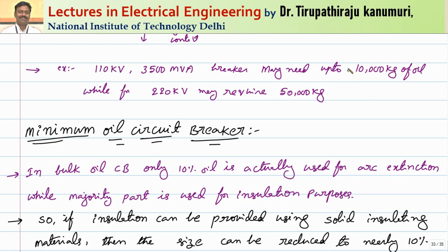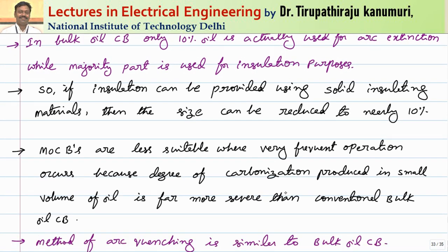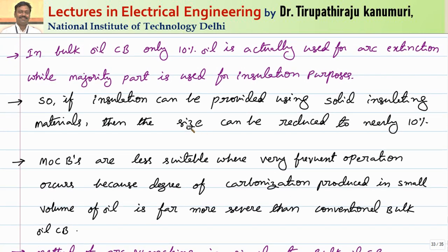They observed practically that out of the total quantity of oil, only 10 percent — nearly 1,000 kgs — is actually used for arc extinction purposes, while the majority of the oil is used for insulation only. Because the tank is made of iron, to insulate between the iron parts and the live contacts, the majority of the oil is spent.